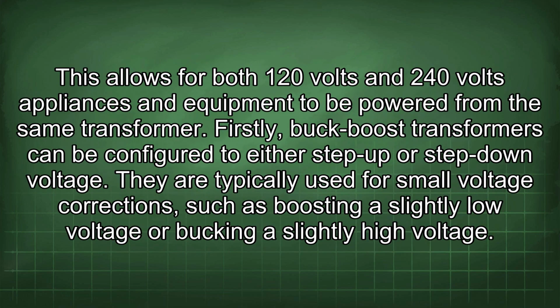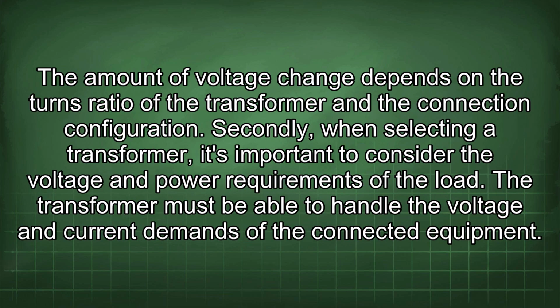This allows for both 120 volts and 240 volts appliances and equipment to be powered from the same transformer. Firstly, buck-boost transformers can be configured to either step up or step down voltage. They are typically used for small voltage corrections, such as boosting a slightly low voltage or bucking a slightly high voltage. The amount of voltage change depends on the turns ratio of the transformer and the connection configuration.